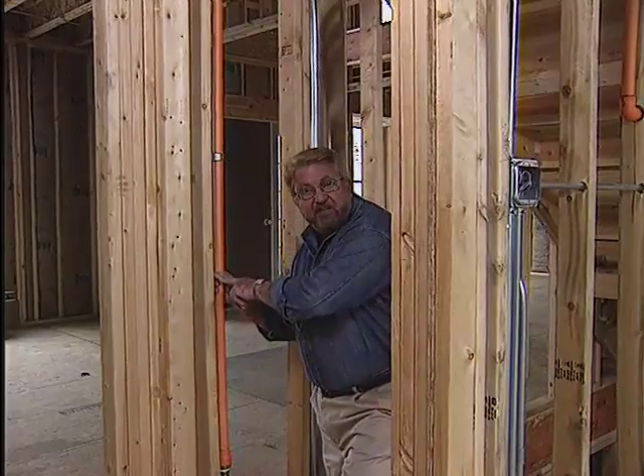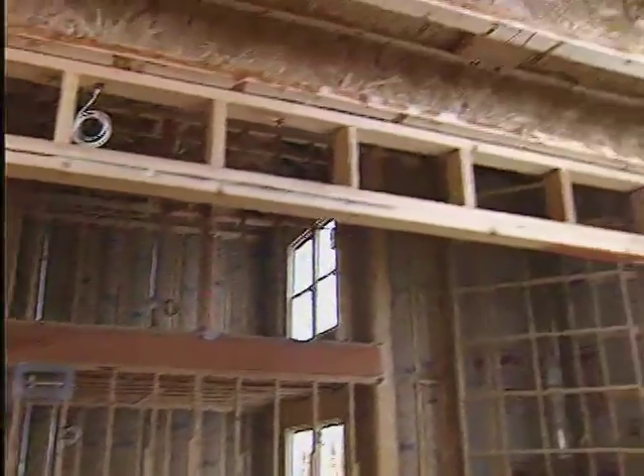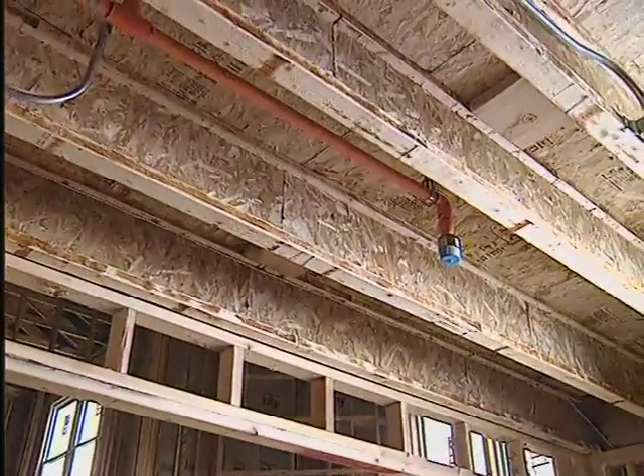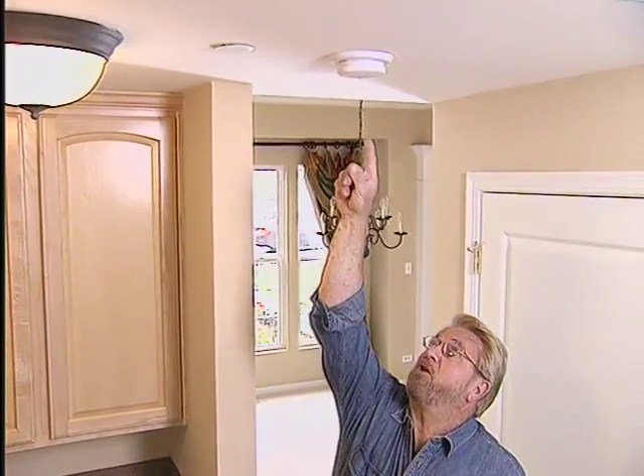We have the one-inch CPVC riser passing through an interior wall going up to the first and second floor. Here on the first floor, the sprinklers will be concealed in the ceiling. At the finished house, you can see how well the sprinkler cover plate blends into the ceiling. It's smaller than a smoke alarm and less obvious than a light fixture. If there's a fire, that heat-sensitive plate just drops away. Each installed sprinkler covers an area at least 12 by 12 feet.